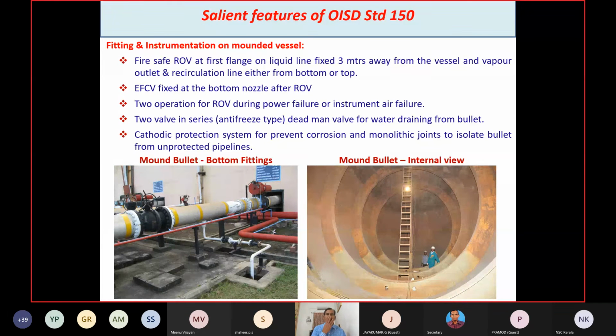So the ROV during power failure or instrument air failure, two operation methods. Actually, during power failure, the ROV should have manual override for opening or closing in case of instrument failure or power failure. And two valves in series should be provided for water draining from the bullet. And a deadman valve also should be provided to ensure the presence of the operator all the time during water draining. And this is the most critical operation as far as all LPG storage is concerned. Many accidents have happened, and two valves in series have to be provided.